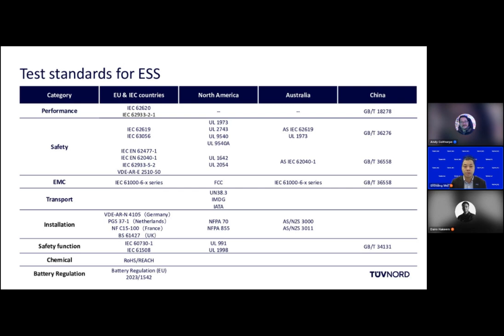There is also a big topic of fire and explosion protection, for which I made a separate table. This is very important for the battery energy storage system because, as we know, to get something on fire you generally need three elements: oxygen, fuel and heat. But the energy storage system doesn't need all three. You can have only the heat and the fuel, which is the battery itself, because the battery is already an energy source, and it can catch fire or explode without oxygen involved. That's also why it is really hard to put out an energy storage system once it starts burning. So a lot of regulations and standards should be considered to validate and test that the battery energy storage system has safeguards against fire and explosions.